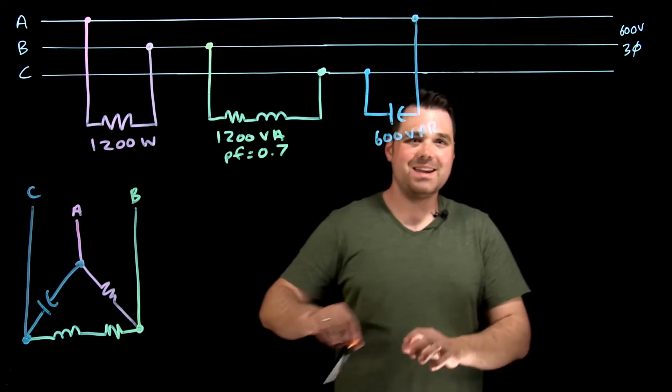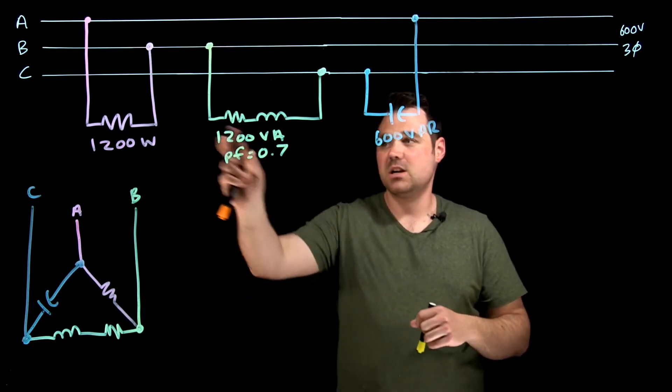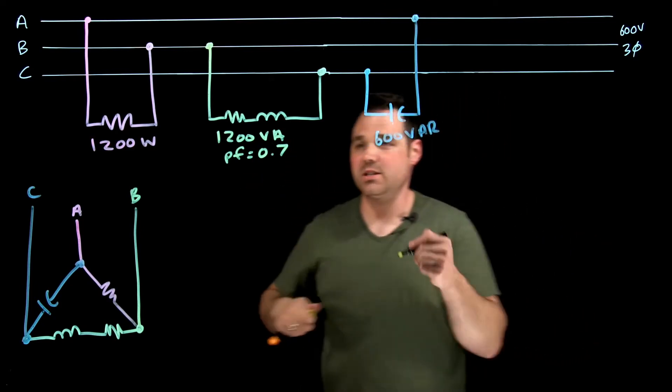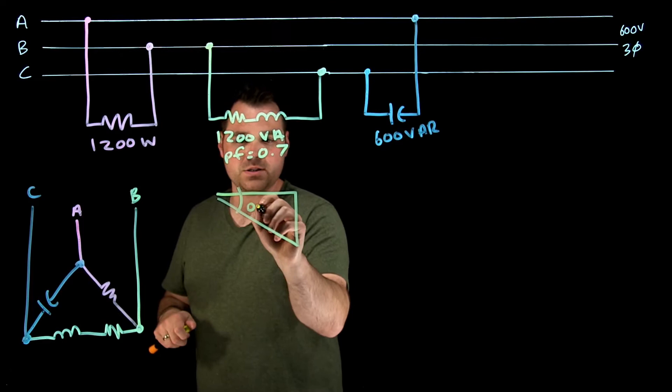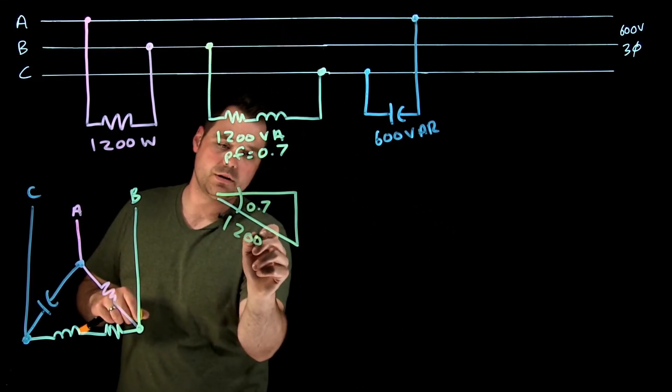But what I want to do here is obviously first thing I'm going to do is break down the B phase. So this is already in watts. I want to find my power triangle essentially for this. So if I've got that, and it's 0.7 is my power factor, and I am 1200 VA.